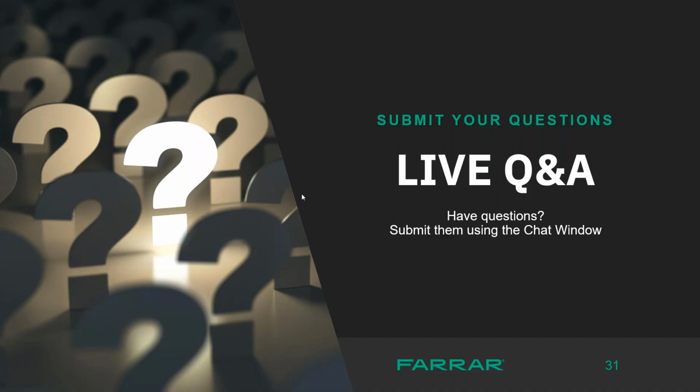Great. All right, we're going to pivot topics. Are there any energy savings or energy efficiency gains from using a large-scale storage suite as opposed to a freezer farm or other type of solution? Absolutely. Because with less equipment, you have less inrush current. Because of the corridor, the ante room, that's going to make your machine sections much more efficient because they have less TD, so it's easier to get down to temperature, with faster recovery time. So overall, you're going to have less energy spend going to a suite rather than a freezer farm.